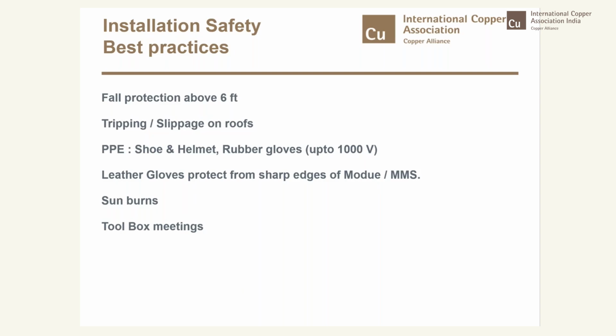He also needs to keep some key installation safety aspects in mind, depending on the height and the other constraints of the building. The fall protection above 6 feet is actually mandated. Anything above 6 feet, you need to have a fall protection for the personal security of the installers. And slippage or tripping on the roofs can happen, so barricade it with proper handrails. Then most importantly, the personal protective equipment has to be there for every operating personnel. It includes the shoe, helmet, and rubber gloves.